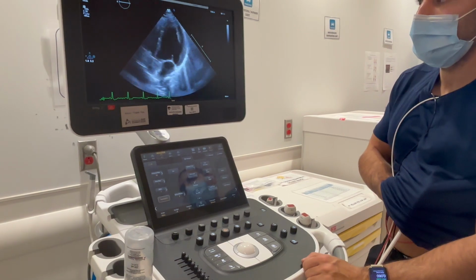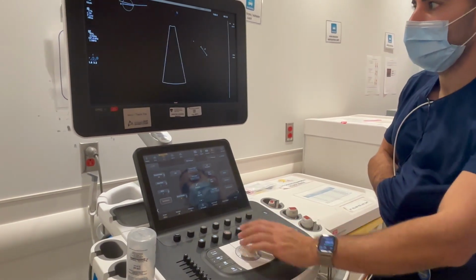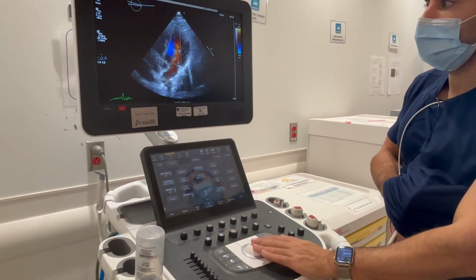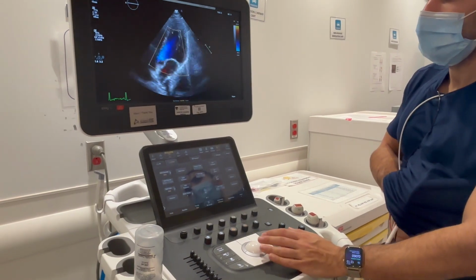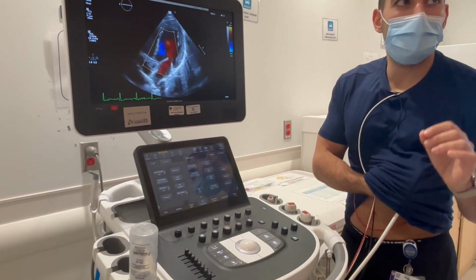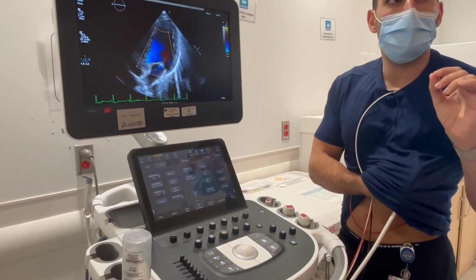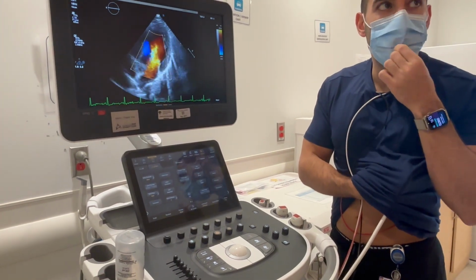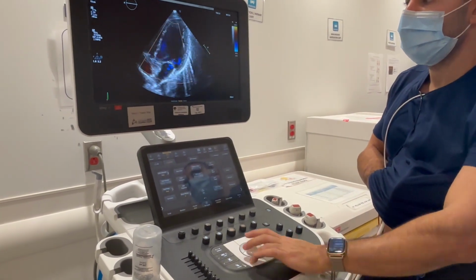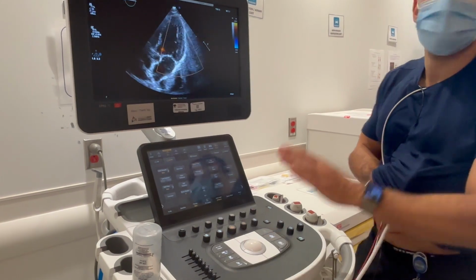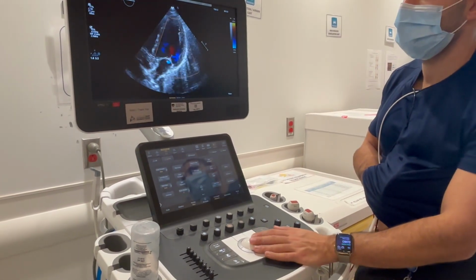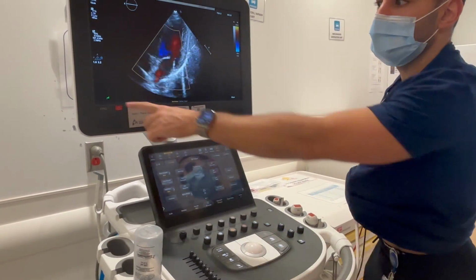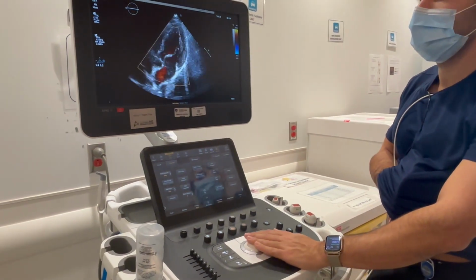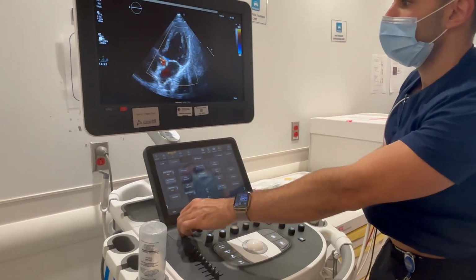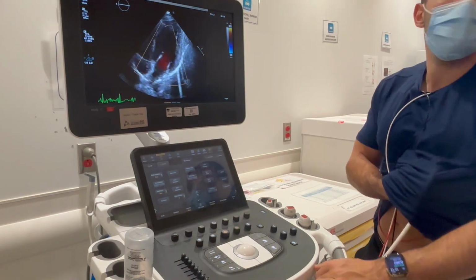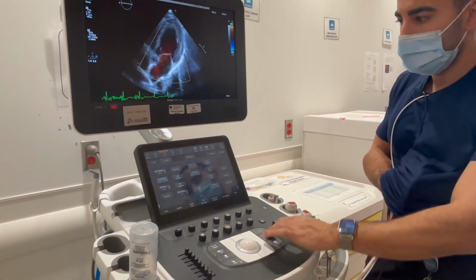Let's say I'm here and I'm doing color. I'm moving my box. I change my box size. Each time I adjust the box of color, it resets my loop. So that's different from GE. In GE, you could just move and it's going to record your movement. In Philips, it doesn't. It actually resets. Each time I move, it resets. So you really have to position your box and adjust what you want, because each time you do an adjustment, it resets your loops.